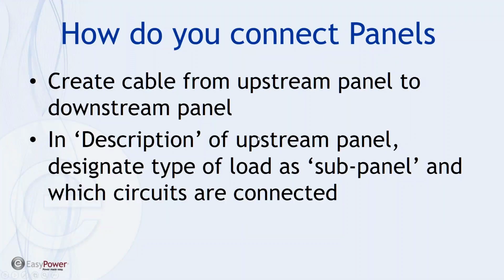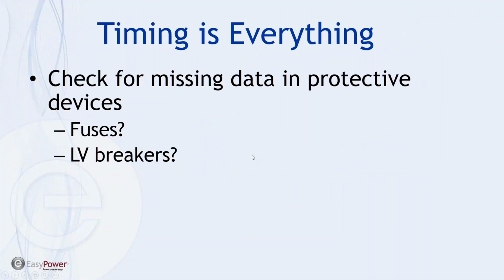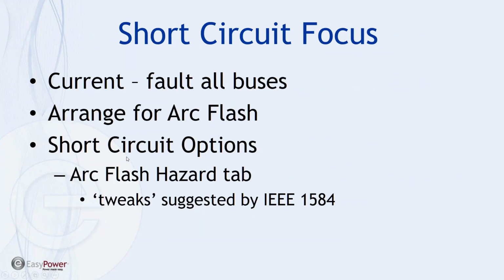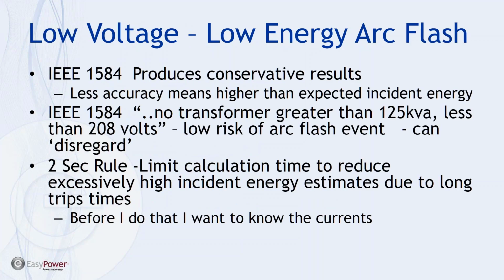So how do we handle arc flash calculations at this point? The fact of the matter is there's not a single phase model yet in terms of arc flash modeling. So right now what we're left with is the IEEE 1584 model, recognizing that there are certain limitations when it comes to low voltage and low energy. And that means that the tool is valid for 208 volts, but the results will be high in terms of incident energy calculations. And if you look at the verbiage in 1584, it says if you're supplied by a transformer less than 125 kVA at less than 208 volts, there's a low risk of arc flash event, or you can disregard those elements.